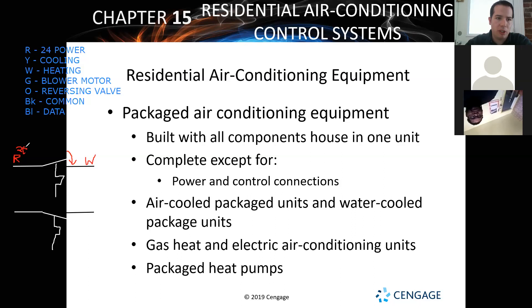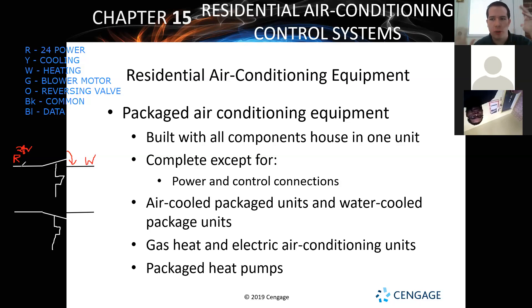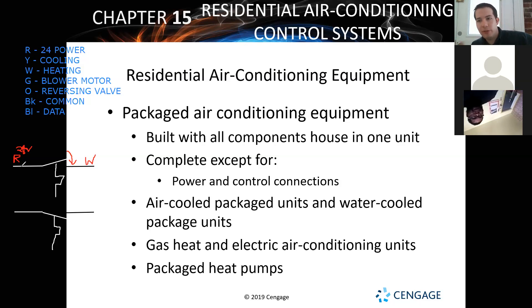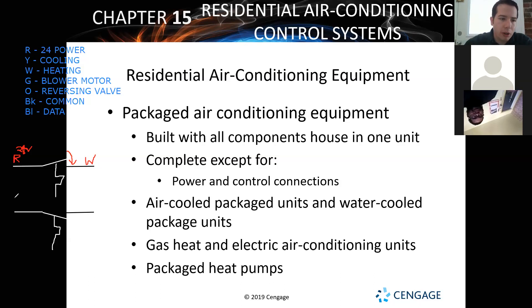This is how the control system works on a residential system: 24-volt power comes from a transformer, and we have to have that 24 volts to do anything. If that transformer blows, the system's done. The thermostat might stay on only if you have batteries in it — if you don't, the thermostat will be off when the transformer blows. A transformer going out is a really common thing to happen and usually knocks out the controls. When someone says 'it's doing nothing, the thermostat's not even on,' your first thought should be: transformer.